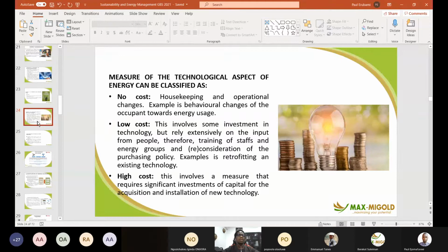For example, how much that generator costs per month, per day, per hour, whatever. You use a factor of that to add to the cost of fuel, then add the cost of your maintenance, and use that to divide the total energy produced in kilowatt hours for that period, and you get your cost per kilowatt hour.